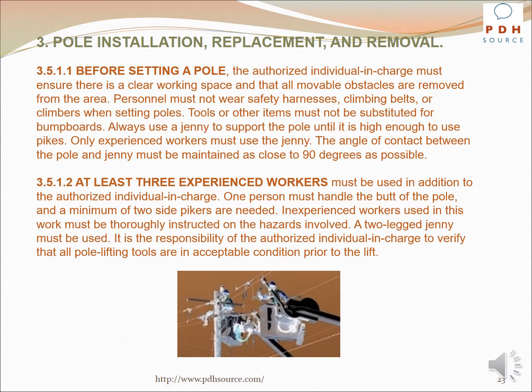Before setting a pole, the authorized individual in charge must ensure there is a clear working space and that all movable obstacles are removed from the area. Personnel must not wear safety harnesses, climbing belts, or climbers when setting poles. Tools or other items must not be substituted for bump boards. Always use a jenny to support the pole until it is high enough to use pikes. Only experienced workers must use the jenny. The angle of contact between the pole and jenny must be maintained as close to 90 degrees as possible.